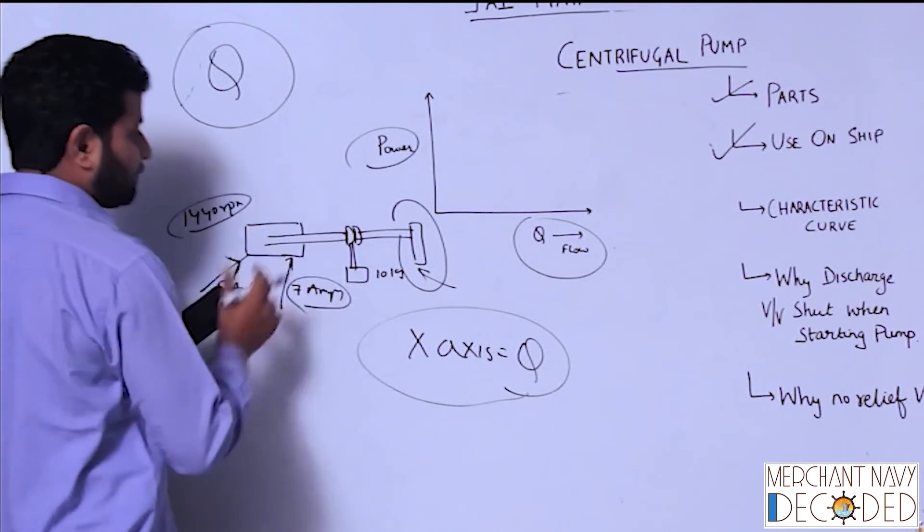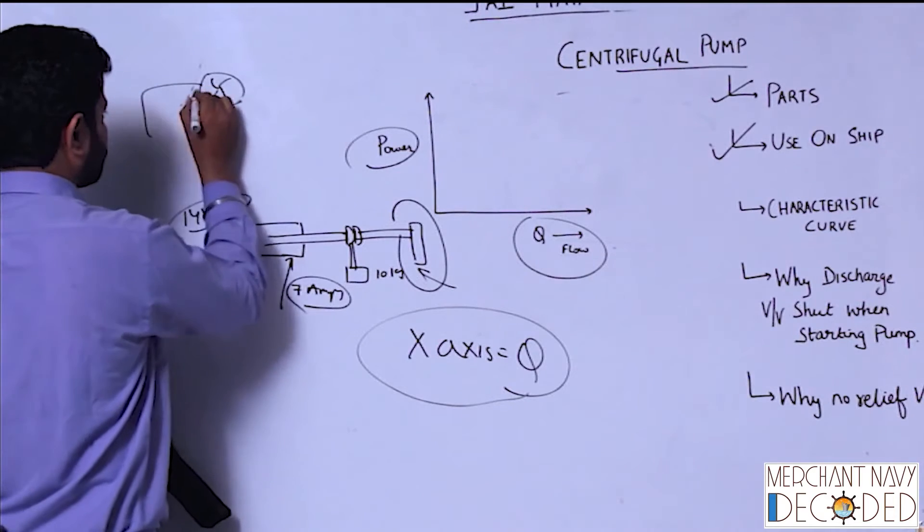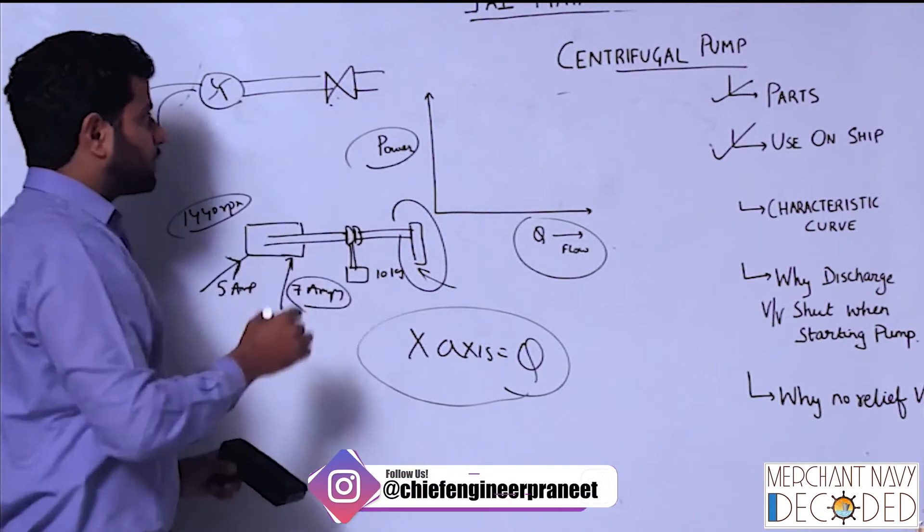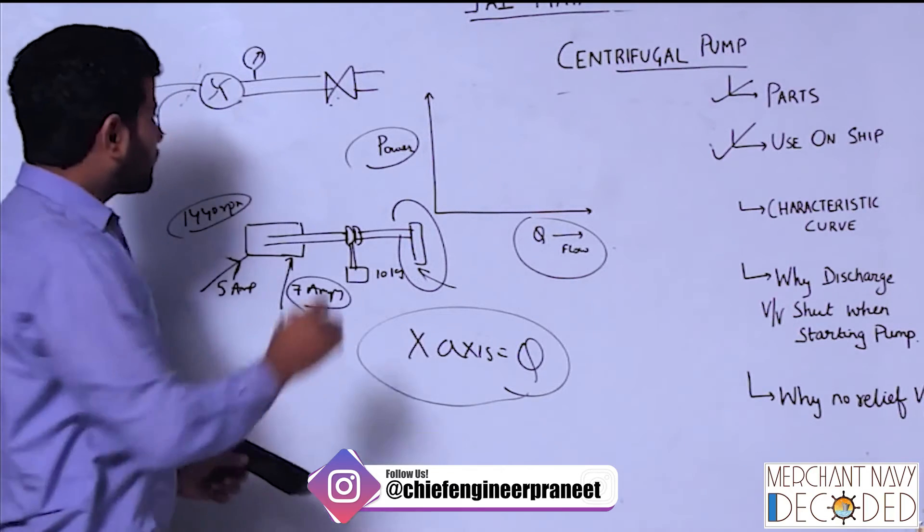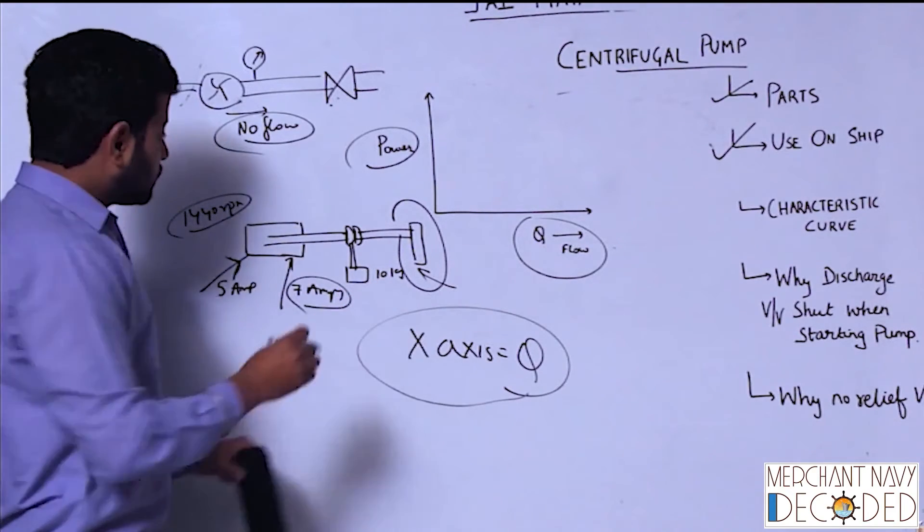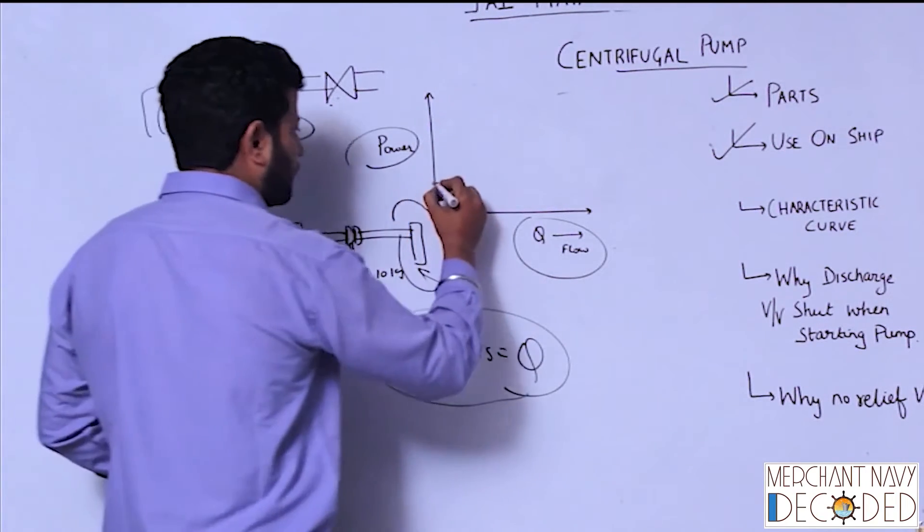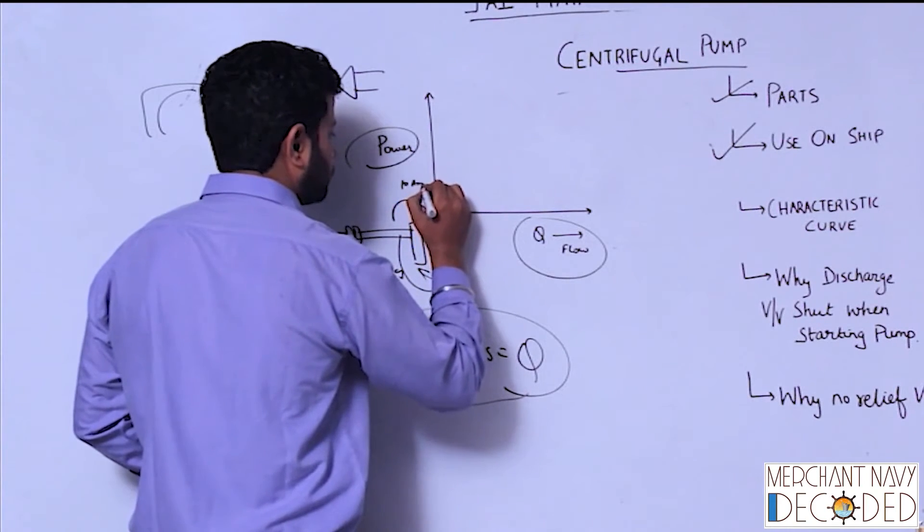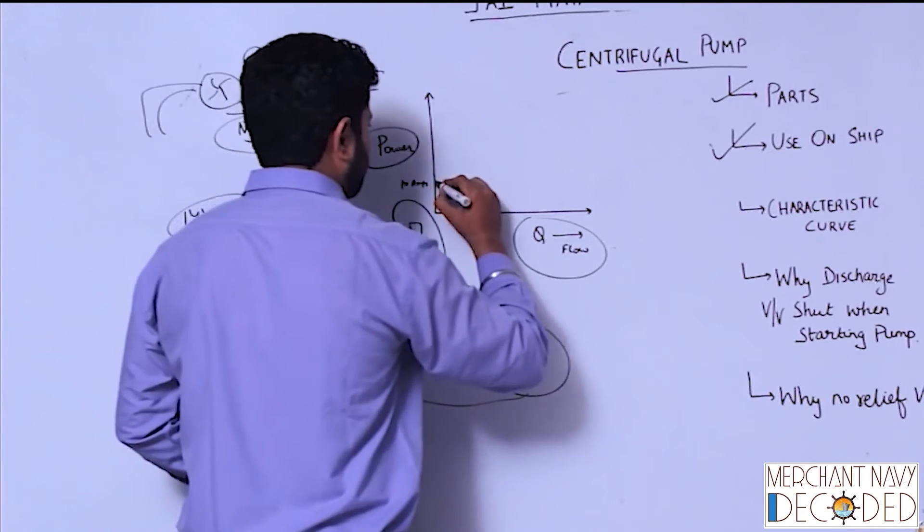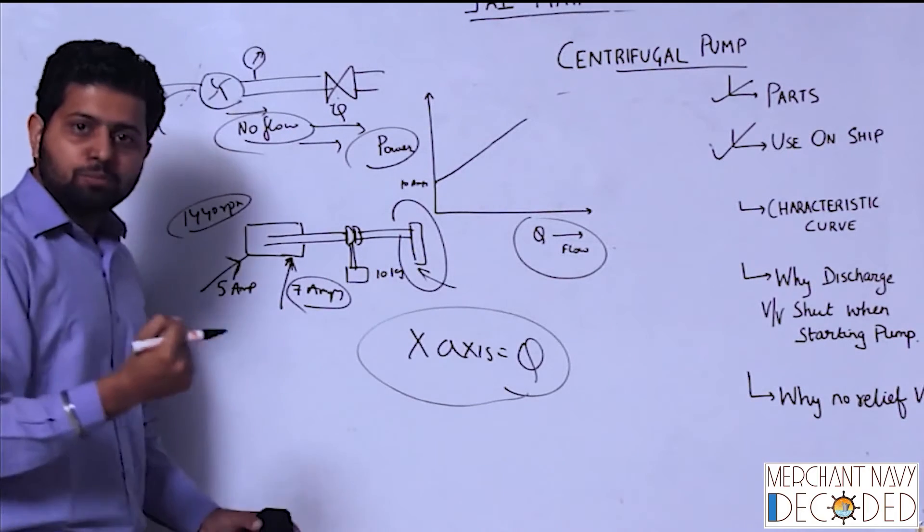Okay guys, so what does that mean? If I have got a centrifugal pump fitted over here and the discharge valve is shut, so what is happening? Discharge valve is shut. So as I told earlier, pressure is going to increase, but since there is no flow, no flow, the motor current that is drawing is minimum. Minimum current, so let's say it's 5 amps.